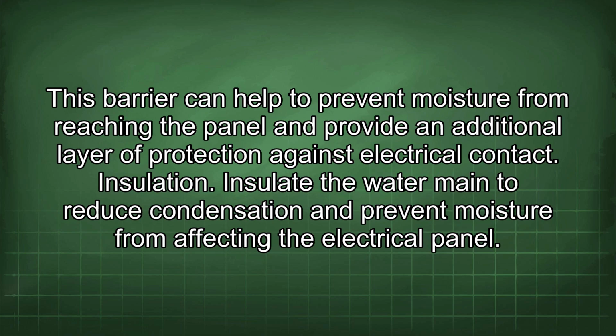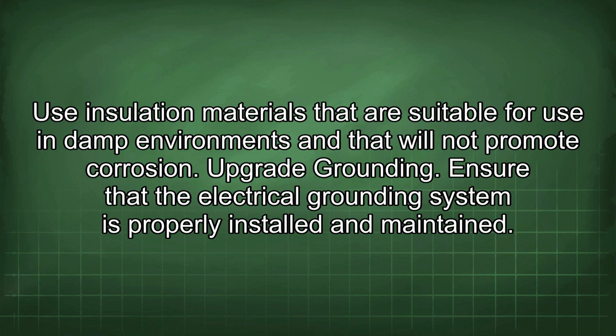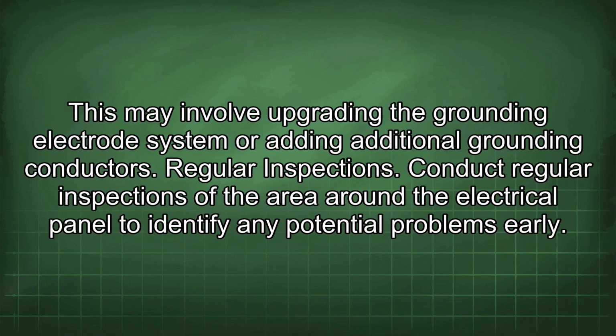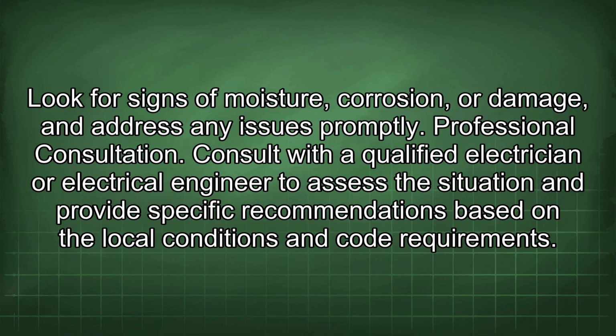Insulation. Insulate the water main to reduce condensation and prevent moisture from affecting the electrical panel. Use insulation materials that are suitable for use in damp environments and that will not promote corrosion. Upgrade grounding. Ensure that the electrical grounding system is properly installed and maintained. This may involve upgrading the grounding electrode system or adding additional grounding conductors. Regular inspections. Conduct regular inspections of the area around the electrical panel to identify any potential problems early. Look for signs of moisture, corrosion, or damage and address any issues promptly.